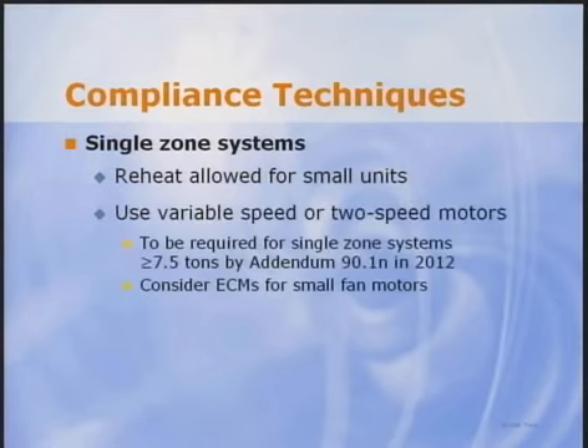For larger systems, variable volume should be considered using either variable speed or two-speed motors. This capability will be a requirement for systems 7.5 tons and larger in 2012. The intent of Addendum 90.1N was to reduce fan energy, but variable volume also improves humidity control. On the next slide, I will show how VAV single-zone systems can be controlled. The rapidly falling cost of electrically commutated motors, or ECMs, which are inherently variable speed, is making it cost-effective to make even the smallest fan coil variable speed. ECMs are also more efficient than standard motors.